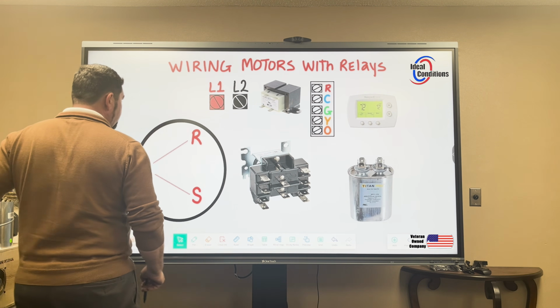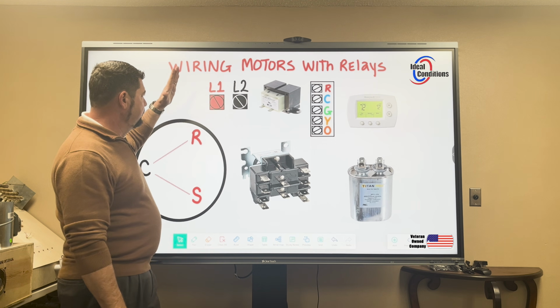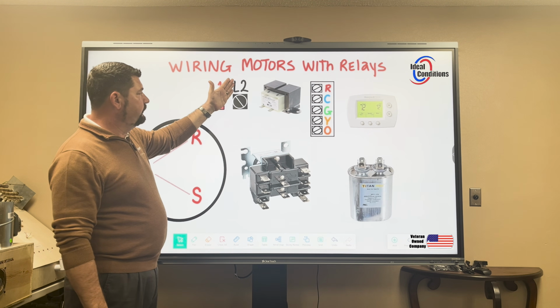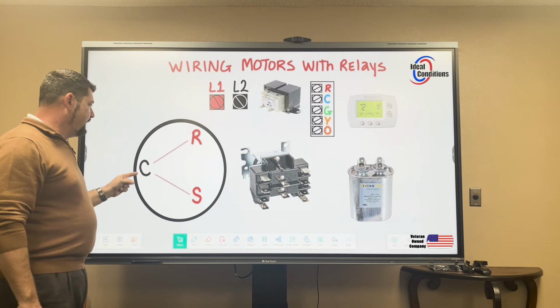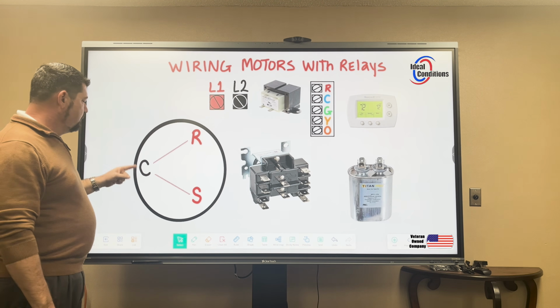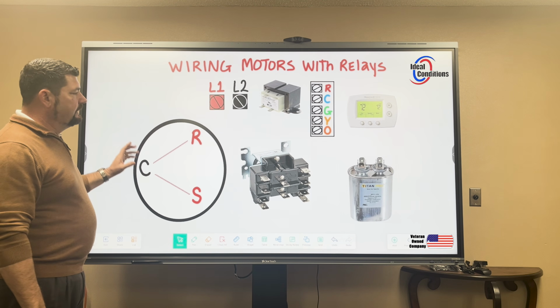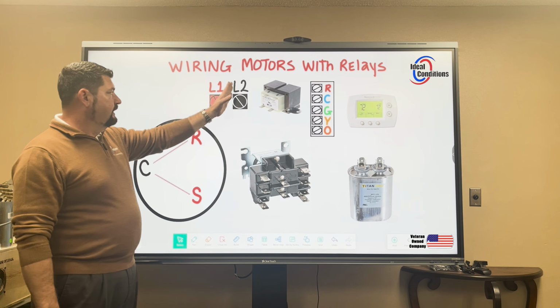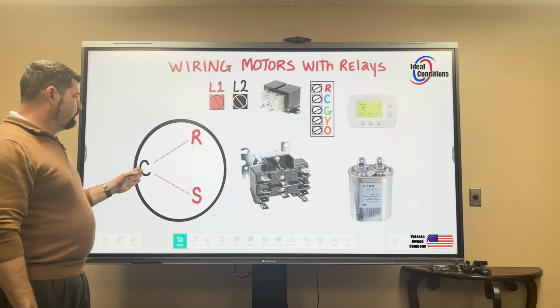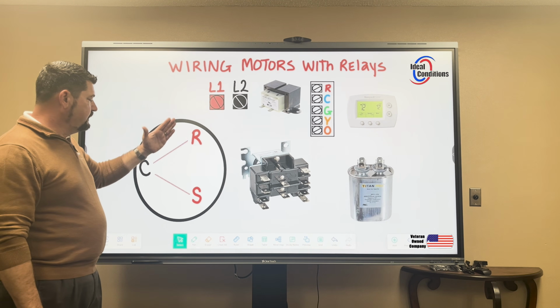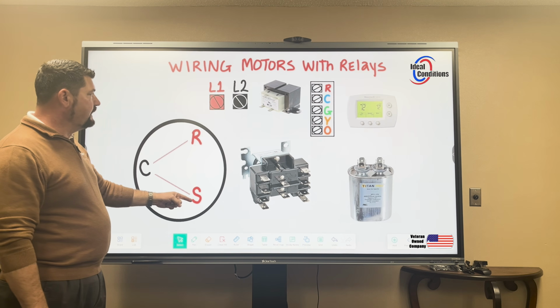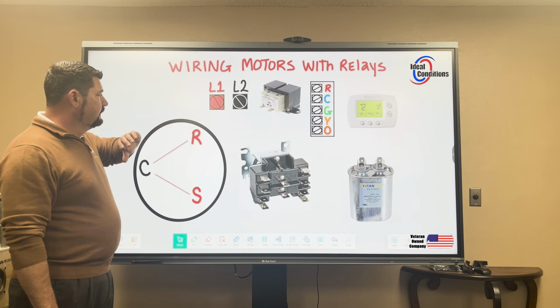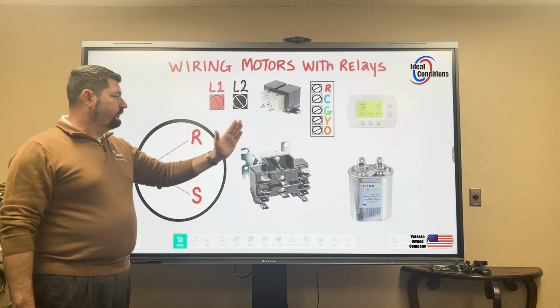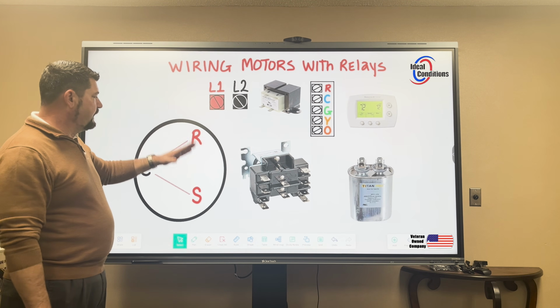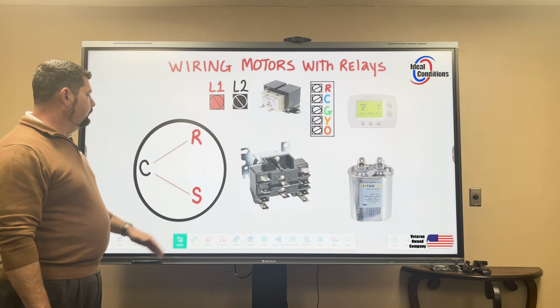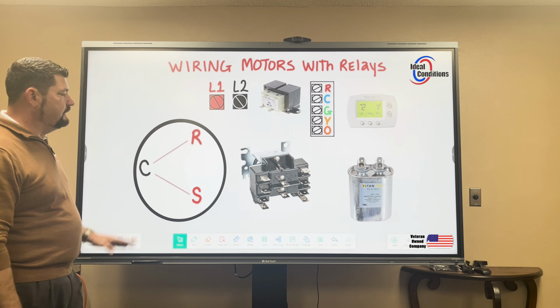As you can see here, L2 I've colored black, and if you look at my motor windings, common, run, and start, my common winding is also black. That's just to help you identify that this leg of power will be applied to common. And if you notice, my run and my start windings are color-coded red, just like my line 1. So as you follow this in the wiring series, you're going to find that L1 is present on these two, and L2 is present on the common.